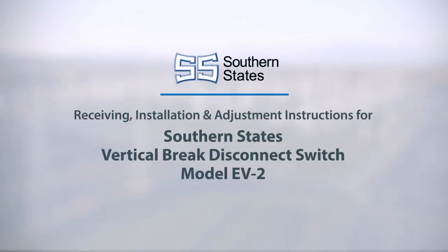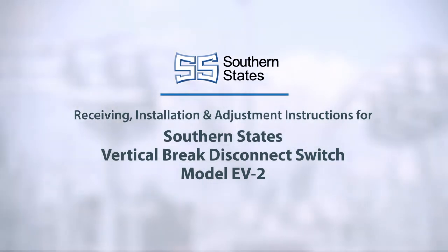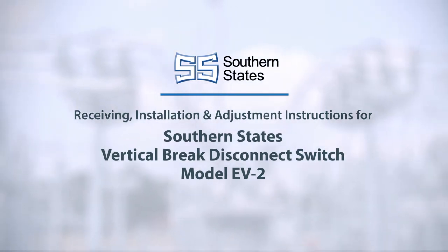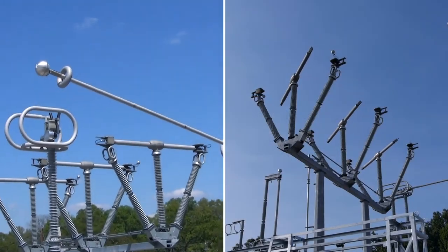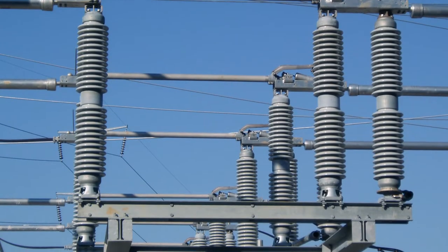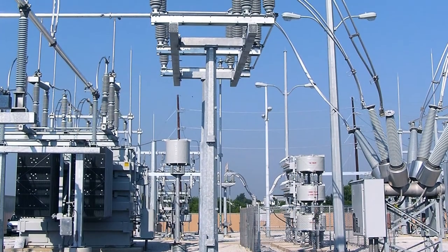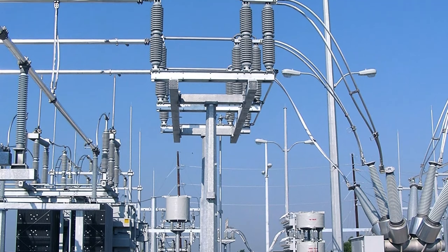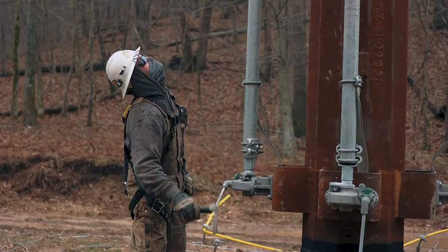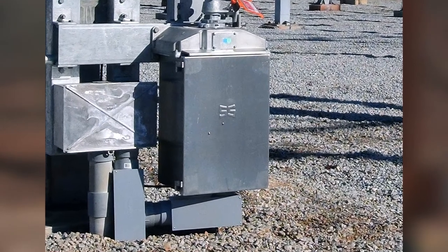The following video contains receiving, installation, and adjustment instructions for Southern States' Vertical Break Disconnect Switch, Model EV2. Vertical brake disconnect switches provide a safe point of isolation for both routine and unexpected maintenance of critical substation equipment. Generally applied as a three-phase solution, operation can be achieved via a manual or motor operator through conventional interface pipe arrangements.